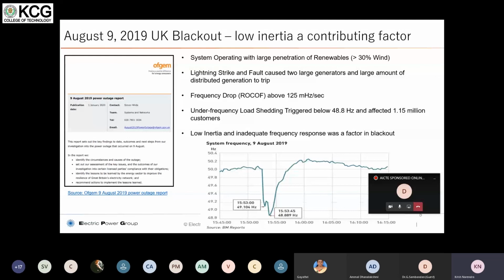As you can see, the frequency has come down to such a level, 48.889, where it operated the under-frequency protection in their system. So the frequency drop was in excess of 125 millihertz per second, which is the ROCOF, which fell very fast. And the under-frequency load shedding operated at 48.8 hertz, which affected about 1.15 million customers.